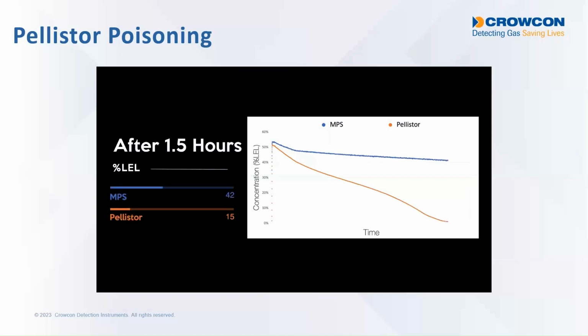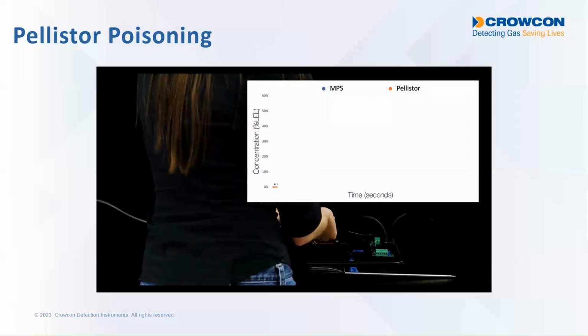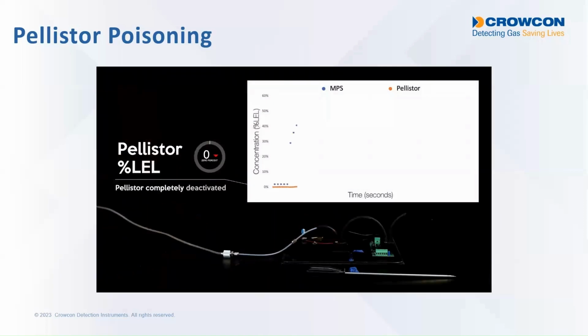And after 1.5 hours, the MPS sensor reading is 42% LEL, and that's because the chamber is not perfectly sealed. Some of the gas is leaking out, but you can see the pellistor is reading 0. It's totally poisoned, completely inactivated by the silicon. And that poisoning of the pellistor is permanent. You cannot recover that pellistor once it's been exposed to silicon.